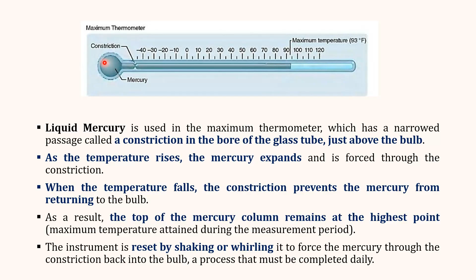But when the temperature falls, this constriction prevents the mercury from returning back to the bulb. As a result, the top of the mercury column remains at the highest point, which represents the maximum temperature attained during the measurement period. And this instrument can be reset by shaking or whirling, which forces the mercury back through the constriction, and it should be completed before the next measurement.